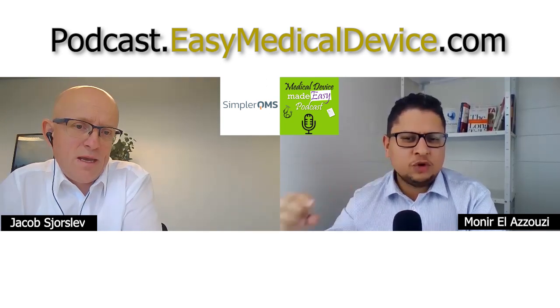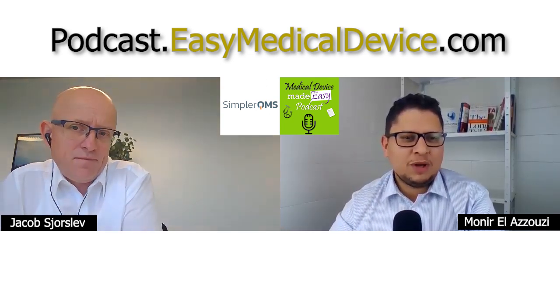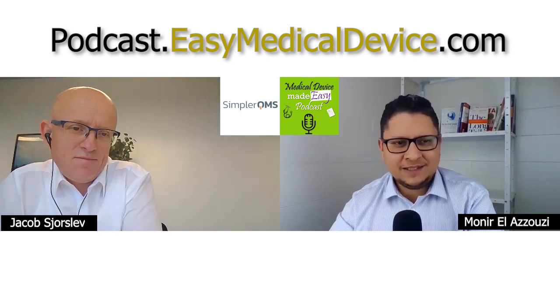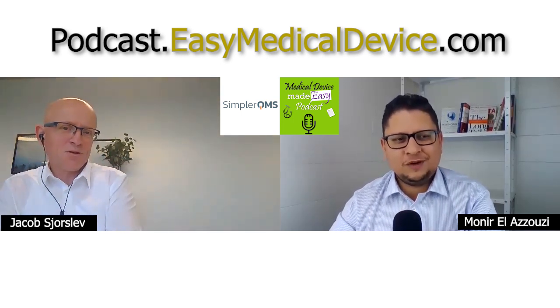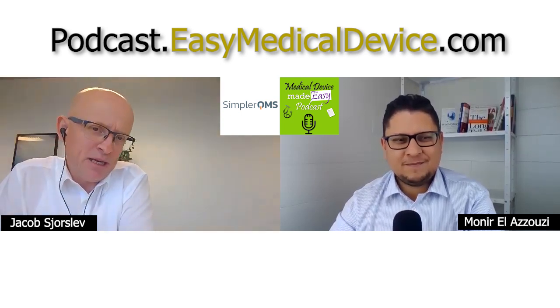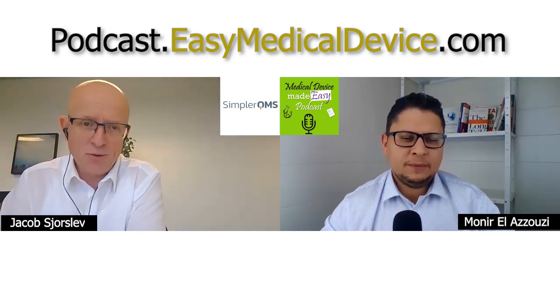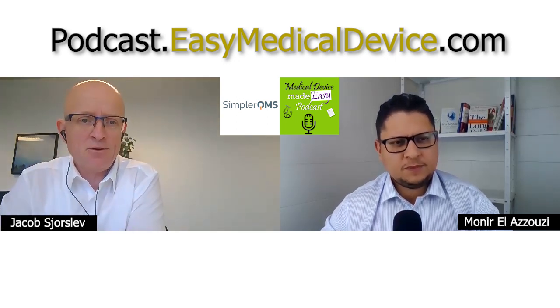Yes. So in terms of validation, that is one thing. I suppose there are a lot of updates also happening with software. So we need to be a little bit more specific on the validation, because one of the things that's very important is training. The first thing as part of the validation is being specific about who needs to be trained in what. Okay. So you have different processes, you map out who needs to be trained in what, and at that point in time you can also make an overview of the training material that you will be using for these people.